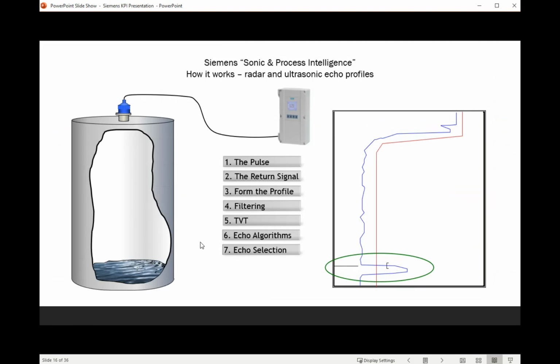That's a key differentiator between Siemens instruments and others out there. If you have a fixed signal reference line, and changing process conditions such as turbulence or some other change in the process or obstructions, a fixed reference line doesn't always give you a true representation of what's happening in the process, because your process is dynamic. The fact that the TVT is calculated each and every time is the key differentiator in what we call process intelligence. Then the instrument is going to apply something called echo algorithms in step number 6.